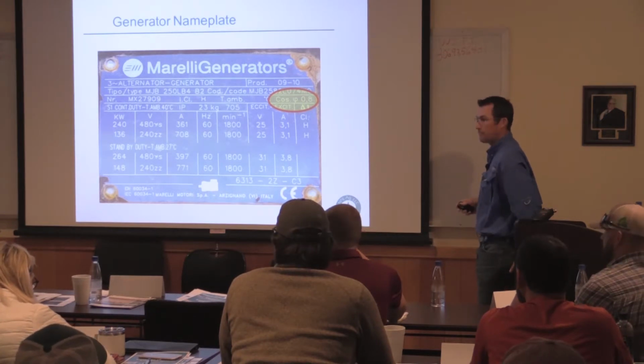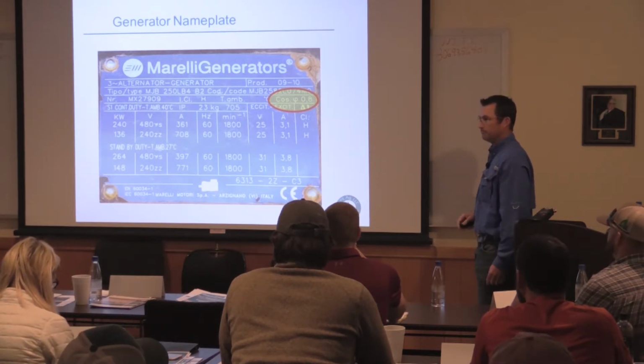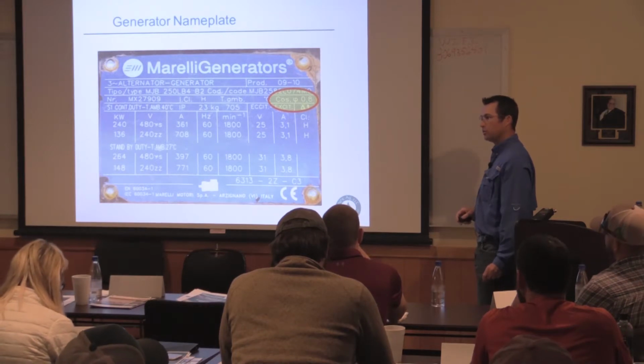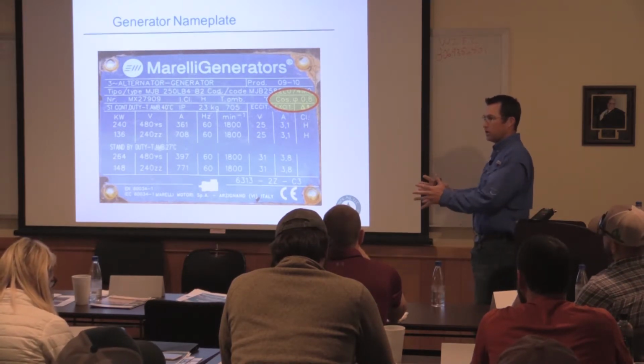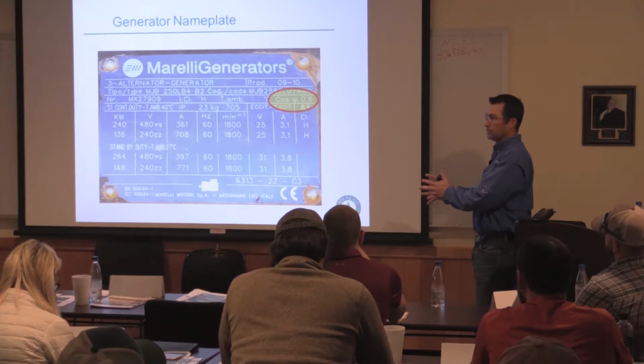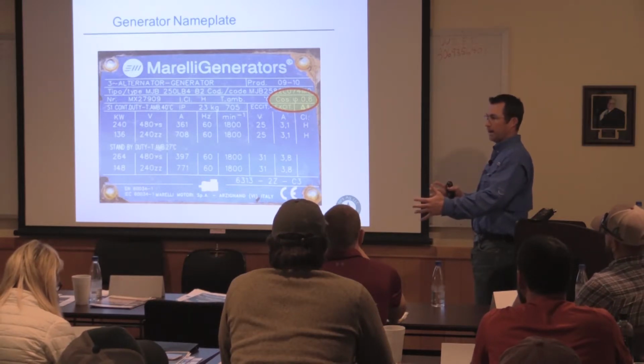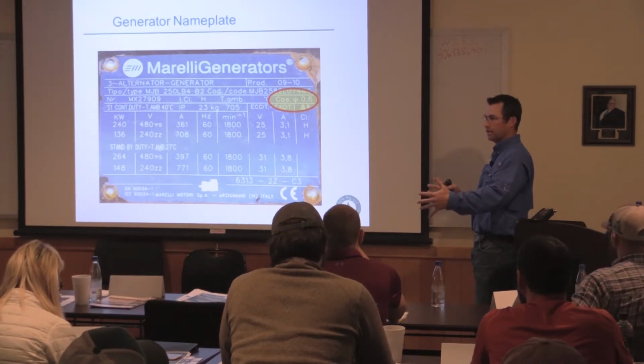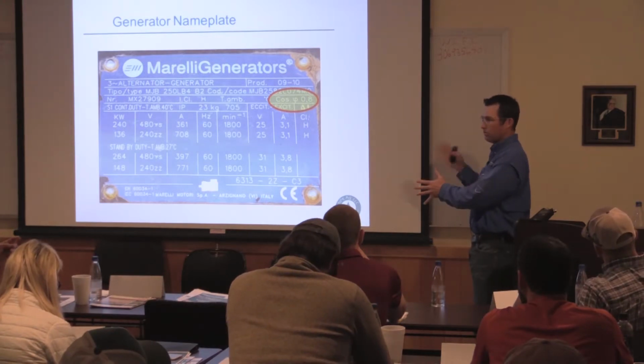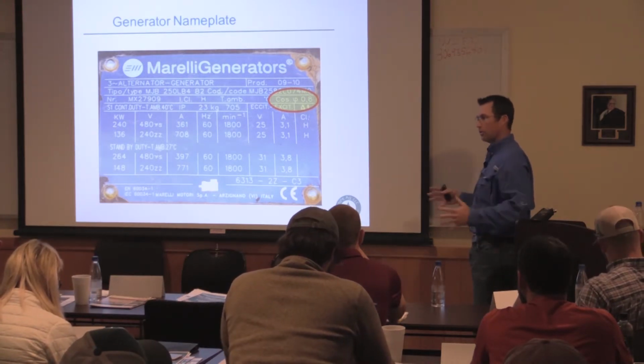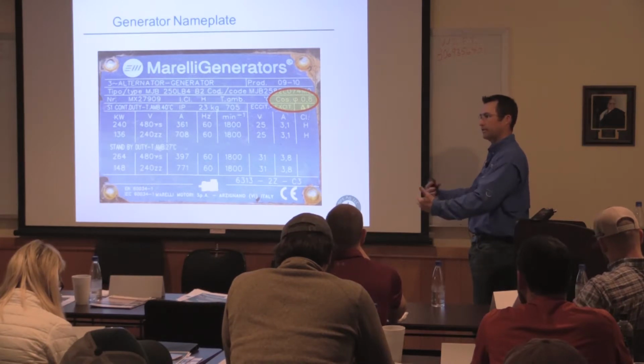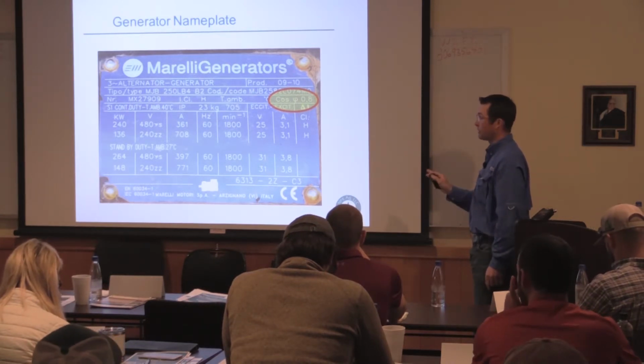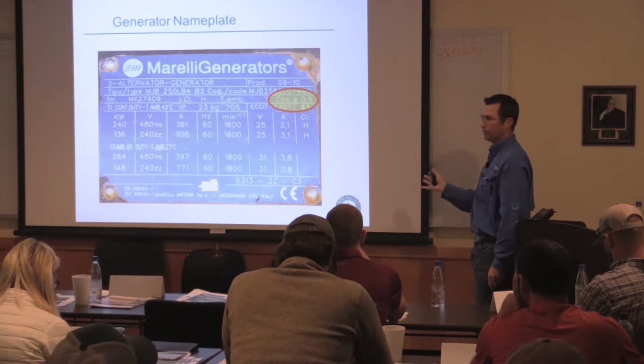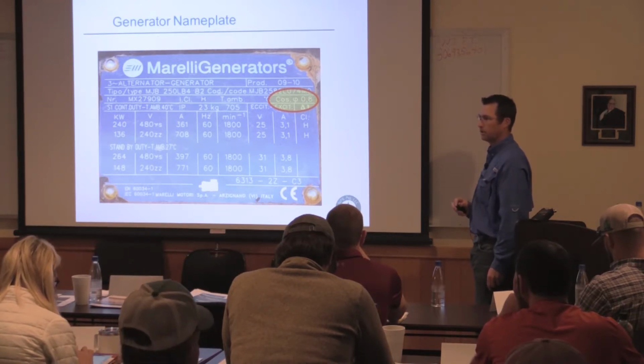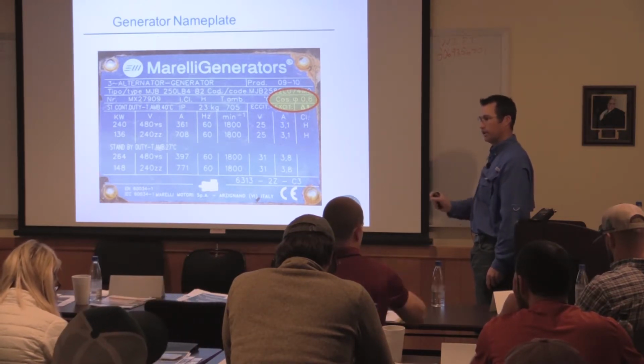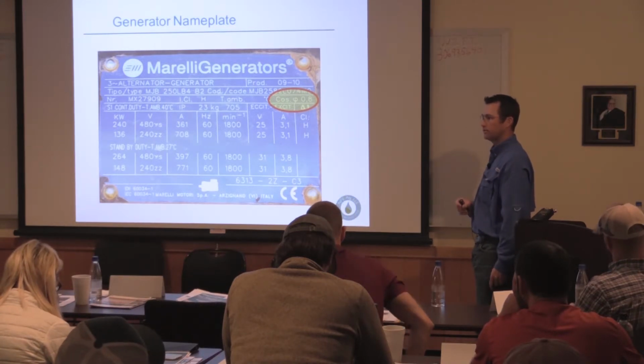Is that kind of standard with all generators? No. More modern ones, yes. Some of the older ones just kind of followed the trend with the electric motors. Some of the older generators, you'd be generating at 0.9 power factor. You would have a problem at the genset. But now they've gotten them tightened up where they're almost at unity power. And then all you've got to worry about is your loads coming back and affecting that power factor. And we'll talk about how you can address some of that too. Variable frequency drives are like magic on this system. And so that's another component that we'll look at to help correct for the power factor, the loading, etc.